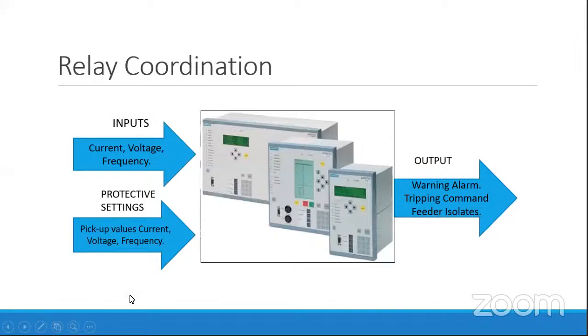Along with this, we can set this relay with certain protection settings, such as the pickup value of the current, voltage, and frequency, in such a way as to prevent our system from being damaged by fault conditions. The measurements will be compared with the protection settings which we have given to this relay, and if any value goes beyond the pickup value, then it will raise the tripping command and isolate the feeder.